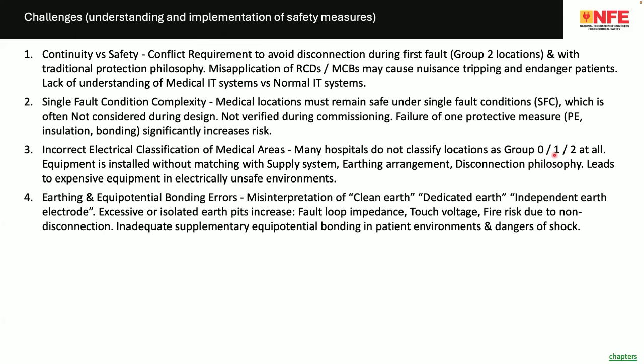You have to read a 2-page document, make a table, put the serial number of the operation theatres, the serial numbers of the ICUs, which come under group 1 location, group 2 location, then classify group 1 and group 2 so that everybody knows how many locations are there. Then the next step is to educate everybody on the minimum requirements for safety in these locations. But if you don't classify, then of course it's very difficult.